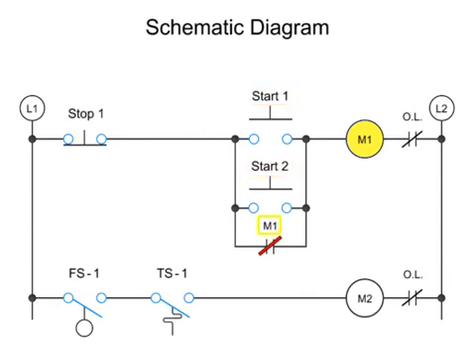There is also control logic associated with normally closed switches. NOT logic occurs when there is a single, normally closed switch in a circuit. Thus, when the normally closed switch, stop 1, operated by a manual push button, is pressed, the M1 coil is shut off and the M1 holding contact is deactivated.